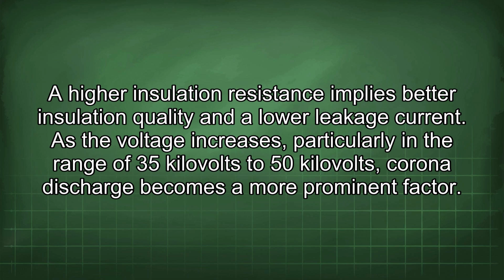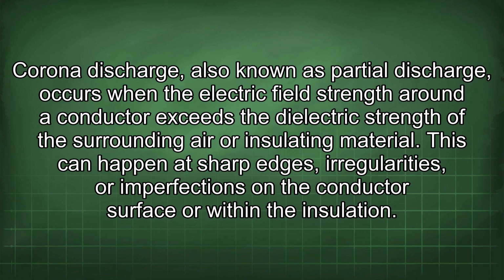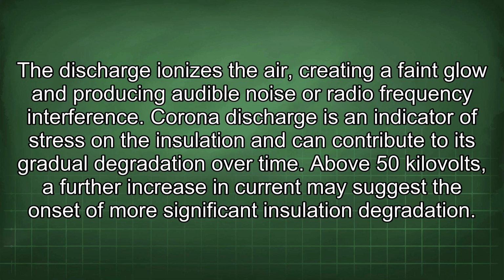As the voltage increases, particularly in the range of 35 kilovolts to 50 kilovolts, corona discharge becomes a more prominent factor. Corona discharge, also known as partial discharge, occurs when the electric field strength around a conductor exceeds the dielectric strength of the surrounding air or insulating material. This can happen at sharp edges, irregularities, or imperfections on the conductor surface or within the insulation. The discharge ionizes the air, creating a faint glow and producing audible noise or radio frequency interference. Corona discharge is an indicator of stress on the insulation and can contribute to its gradual degradation over time.